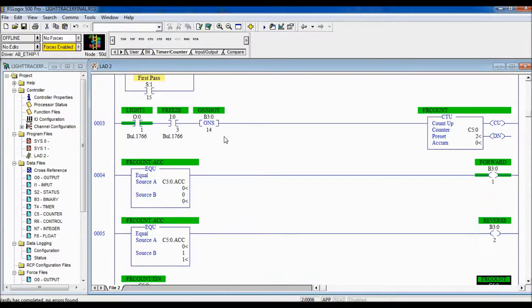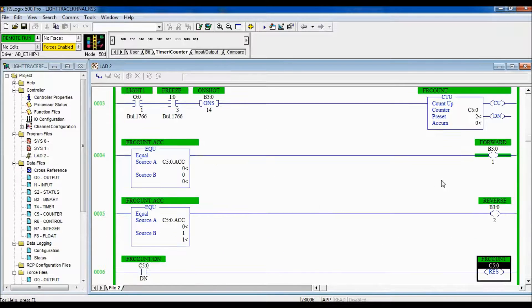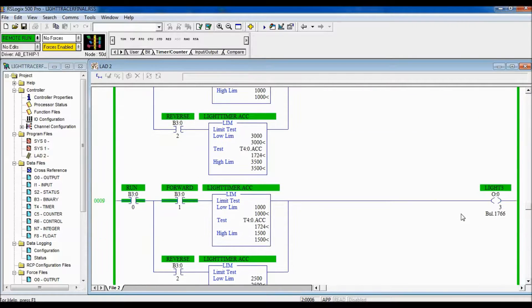I'm going to verify with a check mark to make sure we have nothing wrong. Now we're going to download this program so you can see how it works. The program is downloaded and I'm putting it in run mode. Let's press the start button and watch the run bit come on and the timer start timing. You can see it is timing. Let's go to our output card and you can see them cycling through: 6, 7, 8, 1, 2, 3, 4, 5, 6, 7, 8. Now if I hit my freeze button, you can see it's held at light number three. I let go of the freeze button and it continues its sequence.